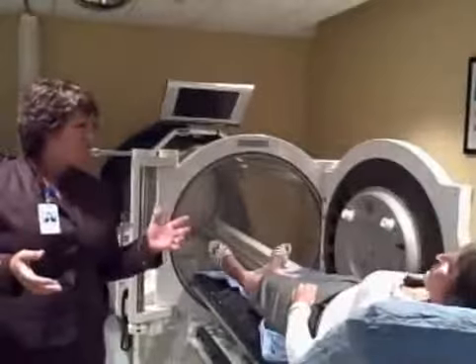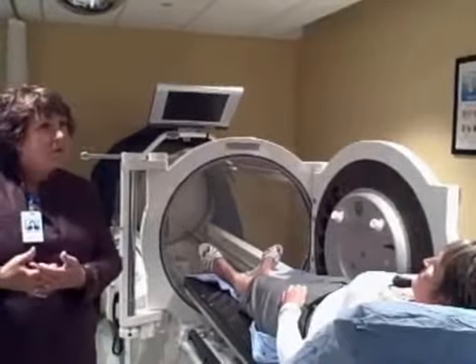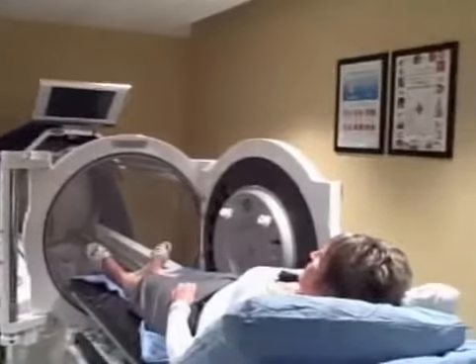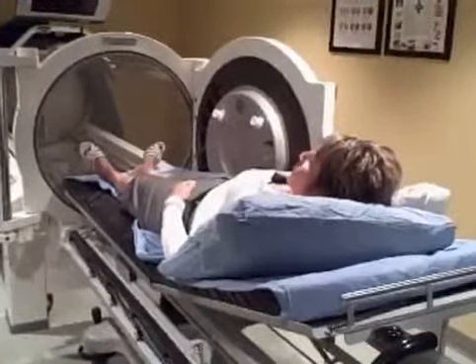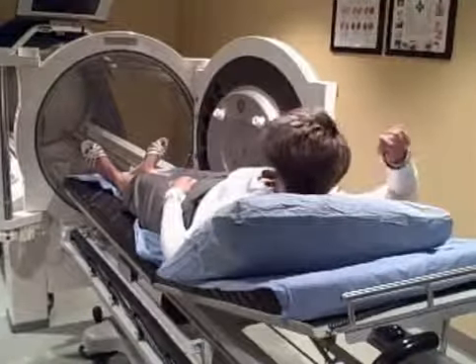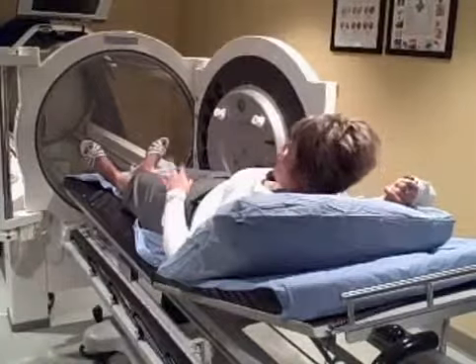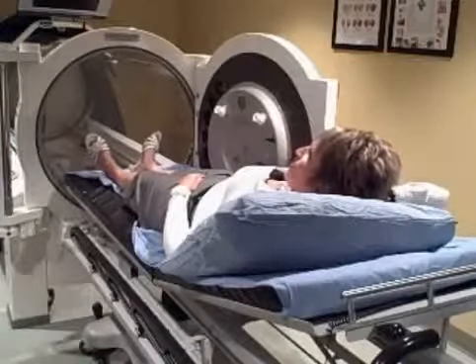Is it kind of like when people have a CAT scan and they can't wear jewelry or any of those kinds of things, but even more restrictions, I assume? Right. Cardiac status has to be stable, a recent pacemaker, we have to make sure that we're looking at the manufacturer of the pacemaker. Something else is we actually put a grounding strap on the patient to make sure that they're grounded to this unit, because static electricity could pose a problem as well.